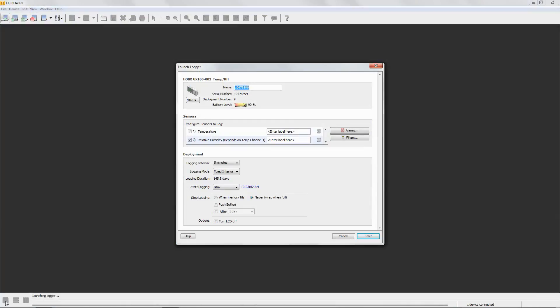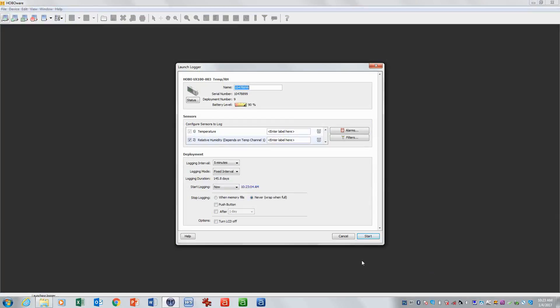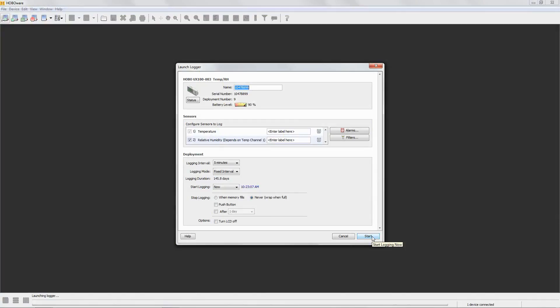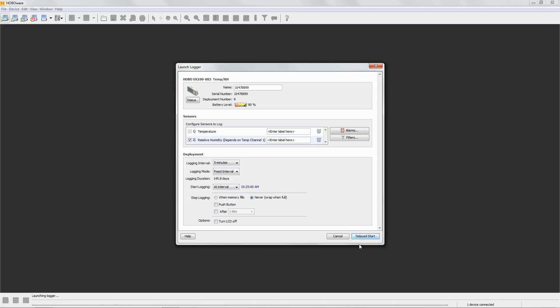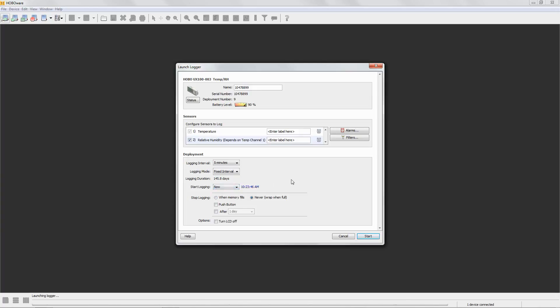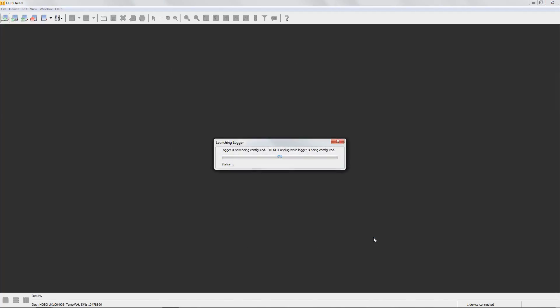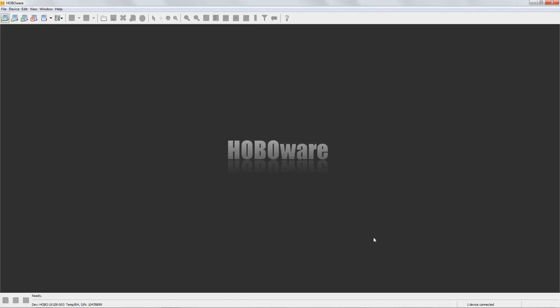To get the logger to start logging, we will tap on or click on the word start down in the lower right hand corner of the launch logger window. Notice it says start here because we're saying start logging now. So if we tap on start it will immediately start logging. If we had changed this to at interval, it changes to delayed start. You see that also on a future time and date, it would say delayed start. For push button, it says button start. It would still go through that same launch status screen, but then you would have to either push the button or wait for that time to elapse before it starts logging. For this example, we'll just say now and again, you can see the time incrementing. That's the time the logger will use as its start time in your data file. So if we click on start, we'll see launching logger and then the logger displays the word load on the screen and then it begins logging data.